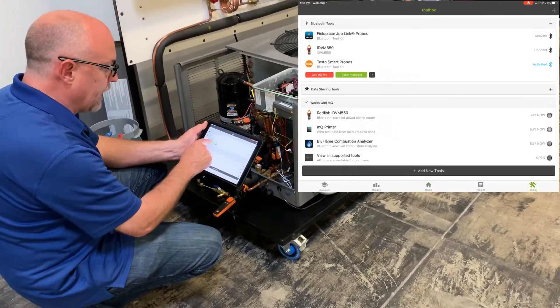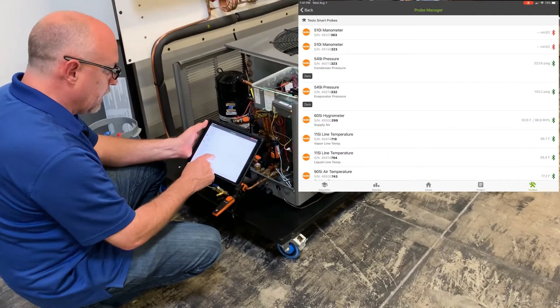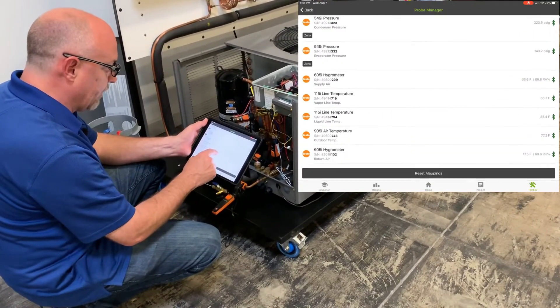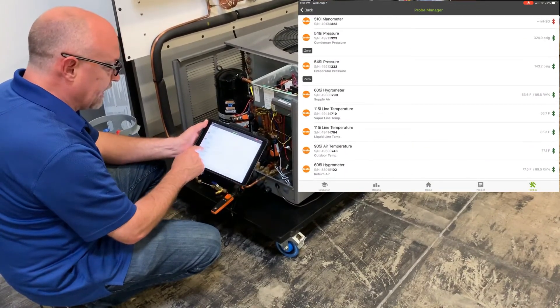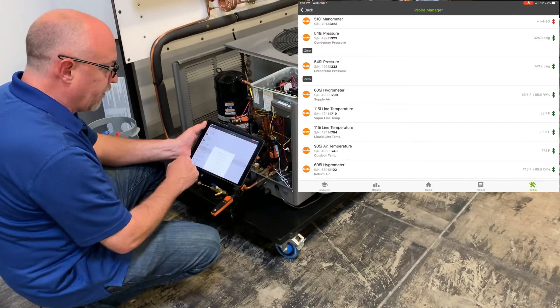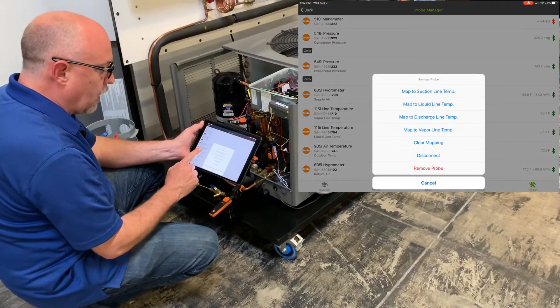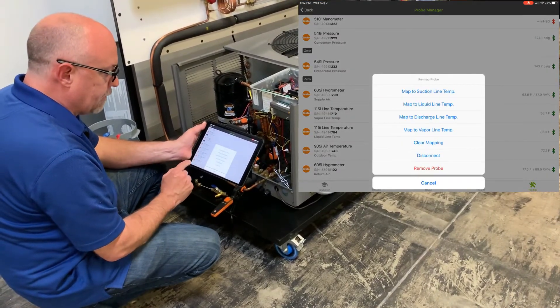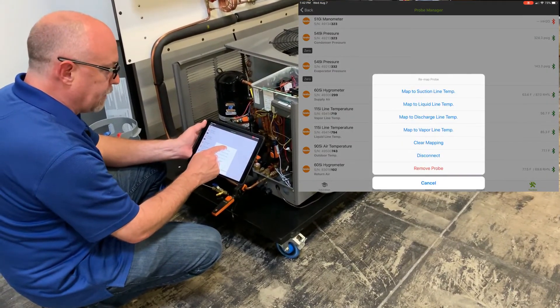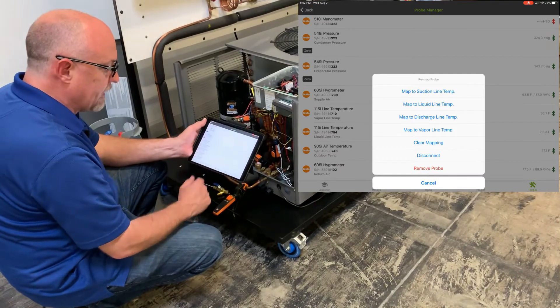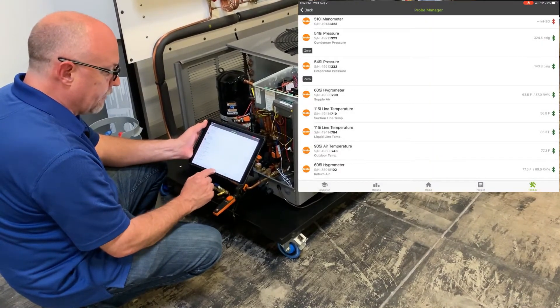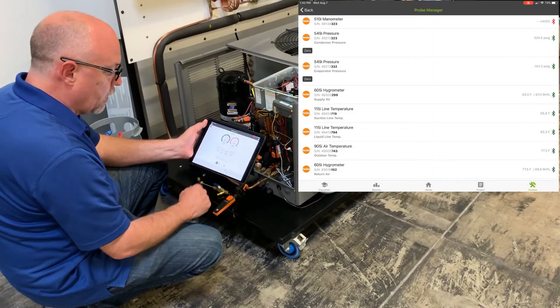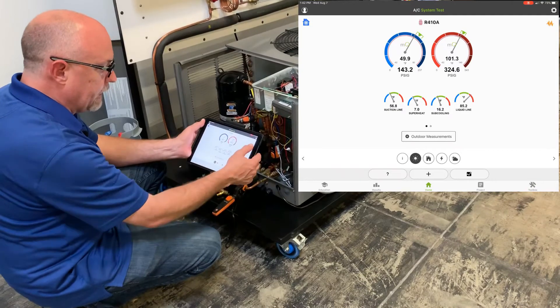I'm going to go to my toolbox, go to my probe manager, make sure that I have all the probes mapped. In this case, I have it mapped for vapor line temperature. You've got to watch vapor line temperatures for the heat pump mode, so I'm going to map that for suction line temp. And that's for the air conditioning mode. Now when I go back, I have superheat. And now you can see I have instability on my application.